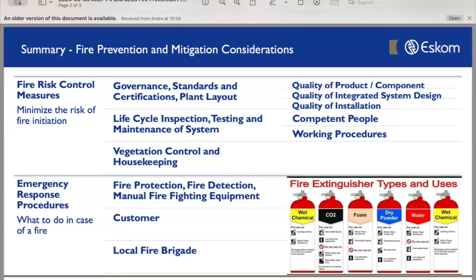Then the second part is emergency response - what to do in case of a fire. This covers what fire protection, fire detection, and manual firefighting equipment you have in the area. It's about understanding that the customer with this equipment, as well as the local fire brigade, need awareness - across the world, in some large-scale BESS incidents, firefighters have been killed because they weren't aware of the explosive gases that come off when batteries burn, not to mention the risk to the customer in whose house some of these systems are installed.